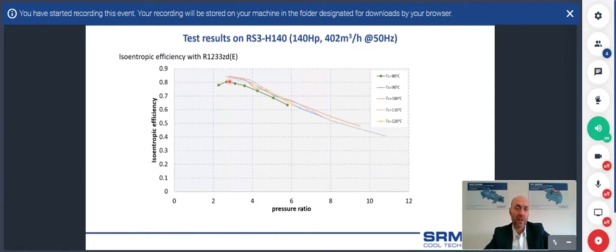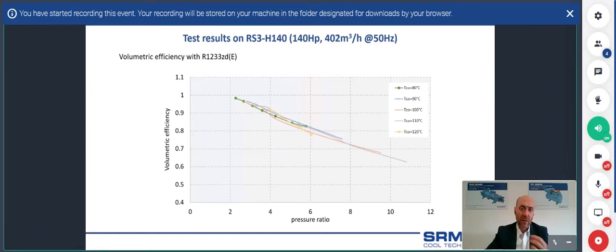So we can define that these compressors are performing in a good way with the 1233 refrigerant. And the smooth shape also indicates that the testing was made in a satisfactory way. So they are not like a wave, but they are smooth shaped. In the same way, the volumetric efficiency is also expressed with the variation of the pressure ratio. Pressure ratio is the ratio between the discharge and the suction pressure. The volumetric efficiency is showing this typical shape for screw compressors, with high levels very close to 1. So from the volumetric efficiency point of view, we can also define that the 1233 is a good refrigerant applied with screw compressors.